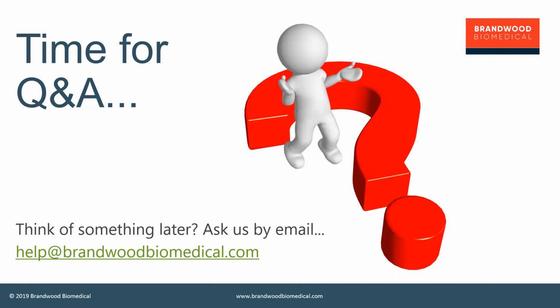Well, that's a really good question, Sarah. Let me say that this has been thought about for quite some time. And I do know that US FDA has some guidance around 3D printed medical devices, and it does touch upon biocompatibility. But the reality is that 3D printing is just another manufacturing process where you convert a raw material into a finished shape. So really there's no difference for doing biocompatibility for something that's made in that process to something that is, say, injection molded.